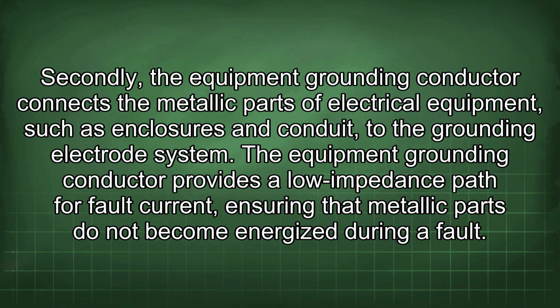Secondly, the equipment grounding conductor connects the metallic parts of electrical equipment, such as enclosures and conduit, to the grounding electrode system. The equipment grounding conductor provides a low impedance path for fault current, ensuring that metallic parts do not become energized during a fault.